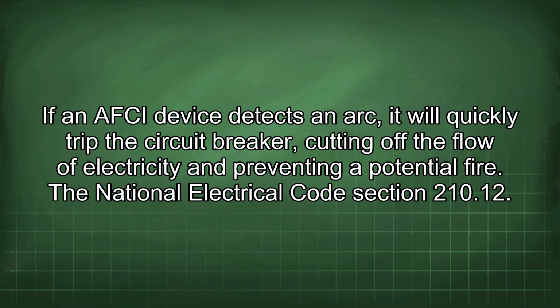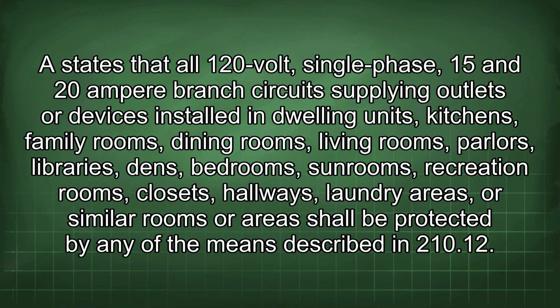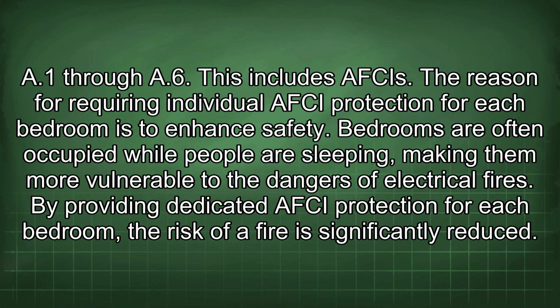The National Electrical Code Section 210.12 states that all 120-volt, single-phase, 15 and 20-ampere branch circuits supplying outlets or devices installed in dwelling units, kitchens, family rooms, dining rooms, living rooms, parlors, libraries, dens, bedrooms, sunrooms, recreation rooms, closets, hallways, laundry areas, or similar rooms or areas shall be protected by any of the means described in 210.12, A1 through A6. This includes AFCIs. The reason for requiring individual AFCI protection for each bedroom is to enhance safety.